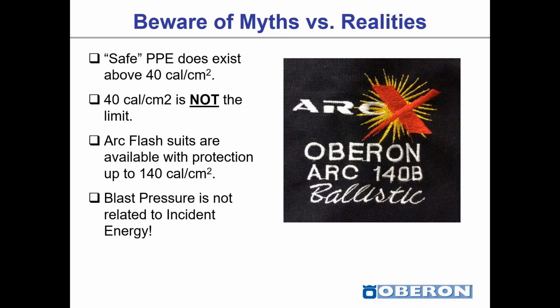Beware of myths versus realities. This is still common in our industry, that we feel there's a limit or a cap at 40 calories. You know, safe PPE does exist above 40 calories. Just this last week, I was testing at Kinectrics with Oberon, and we were exposing products up to 117 calories without getting any burns. That was a 100 cal suit hood that we were testing. We couldn't actually get any burns. We were testing as high as we could. In the past, Oberon has certified a 140 calorie ballistic arc flash suit. So safe PPE does exist above 40 calories. It's not a limit. And really the arc flash incident energy does not directly correlate with the blast. I could spend a whole webinar topic on just this alone, but it's important to note that blast pressure is not related to the incident energy.